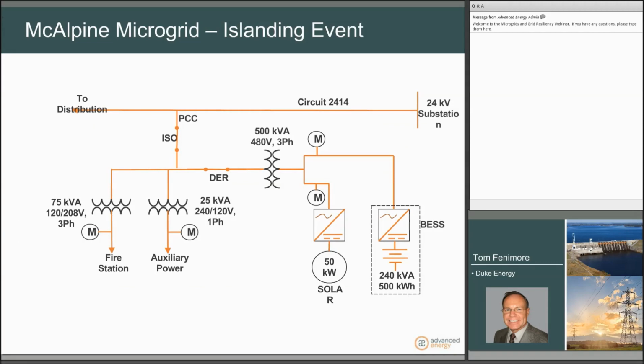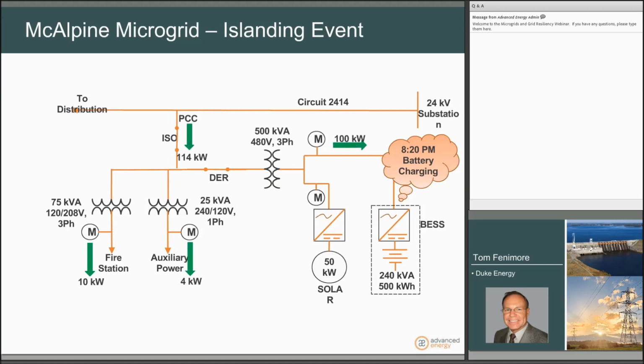The actual islanding event process that takes place when we do disconnect from the microgrid and support the fire station looks like this. This is the actual first event that we had at the fire station on April 30th of 2016. At 8:20 p.m., the battery was charging on a Saturday evening, and the battery was charging at 100 kW. The fire station load was 10 kW.